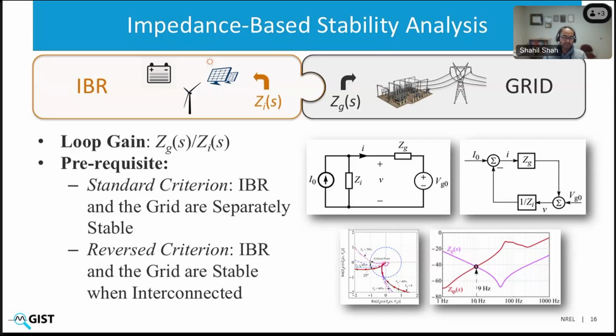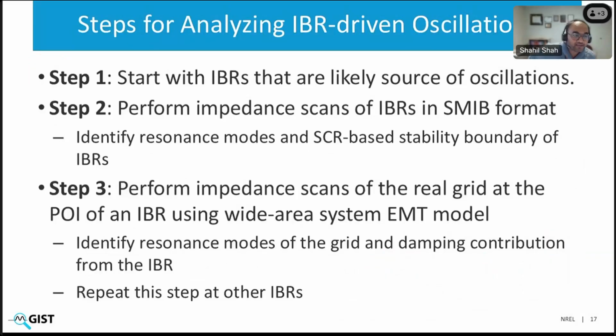The second criterion is the reverse criterion, where we assume that the IBR and grid, when they're connected, are stable together. Now, what happens to the stability of the grid if we disconnect the IBR? So we are really trying to understand if removing the IBR is causing any instability, or if the IBR is basically a stabilizing device. I won't go into more details, but these two criteria together are very complementary. They enable the impedance-based stability analysis to apply to large systems in a feasible manner, where it can work on real systems.